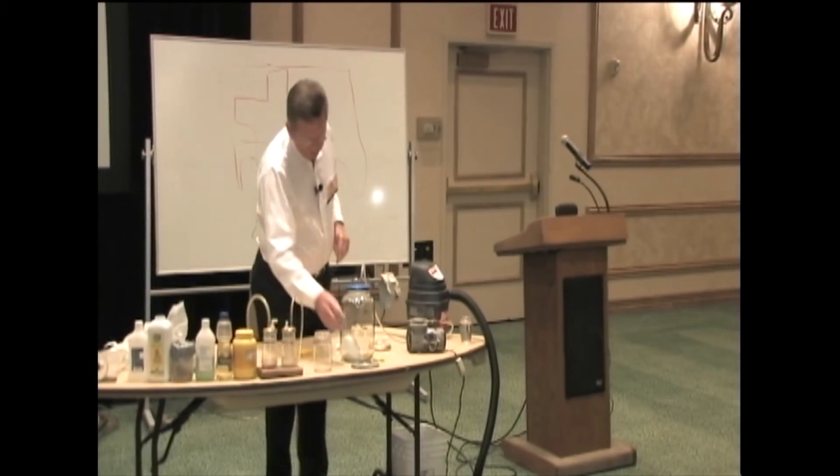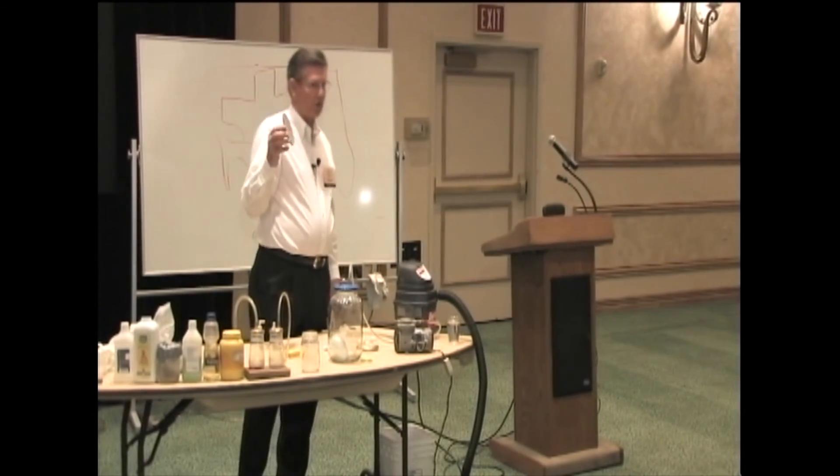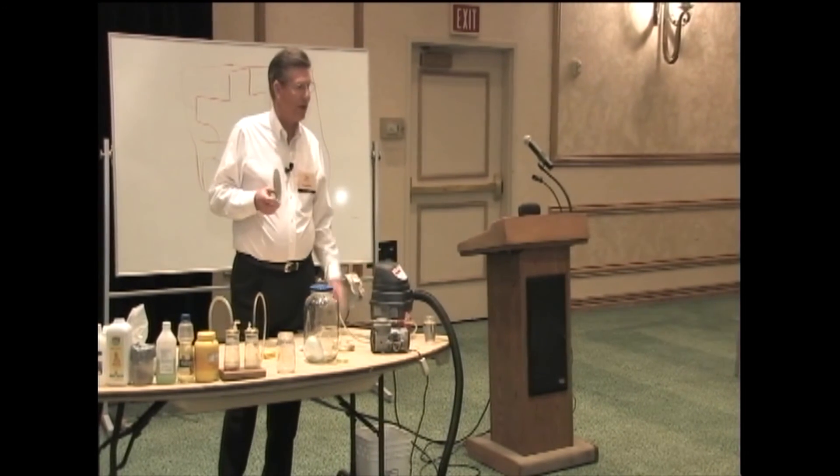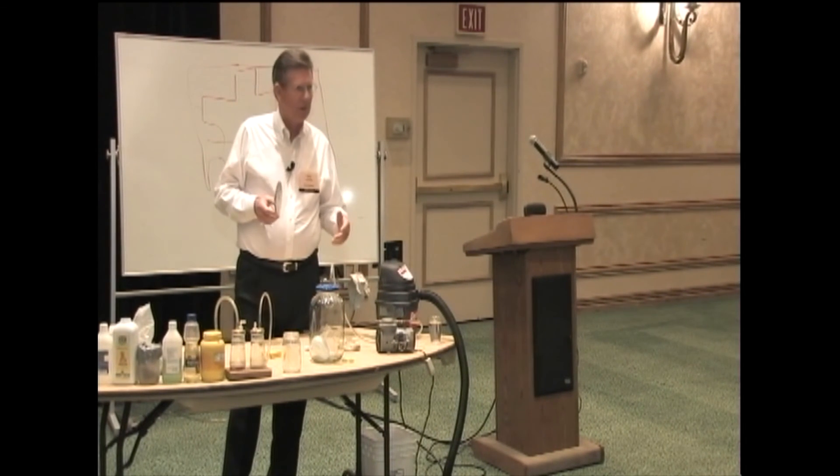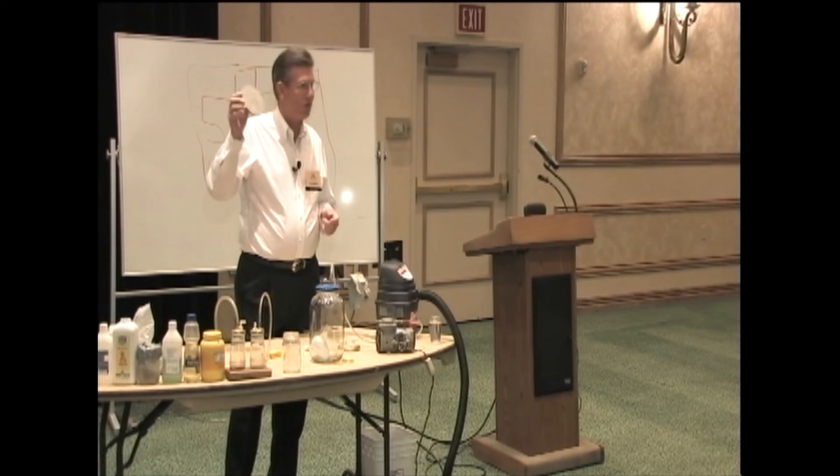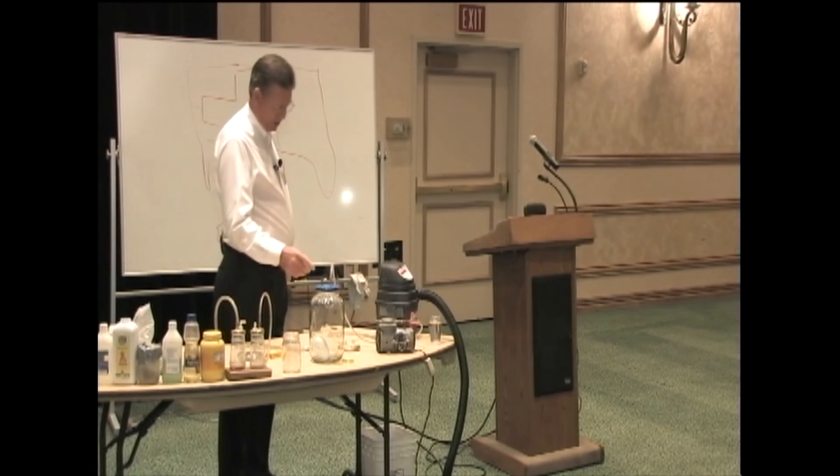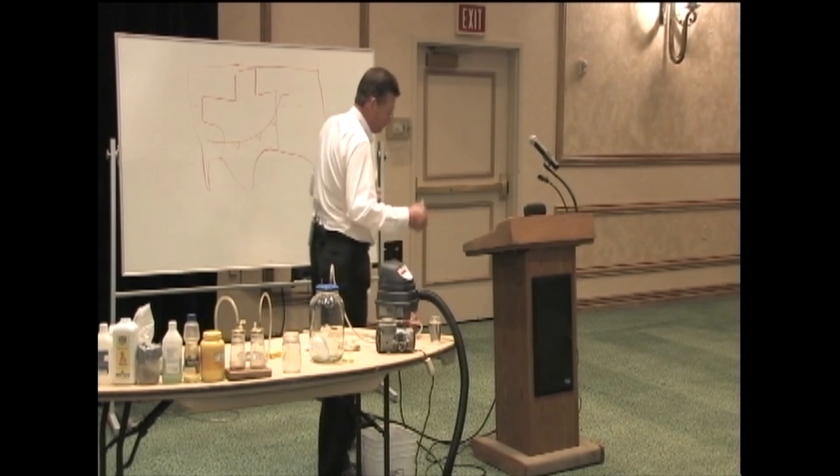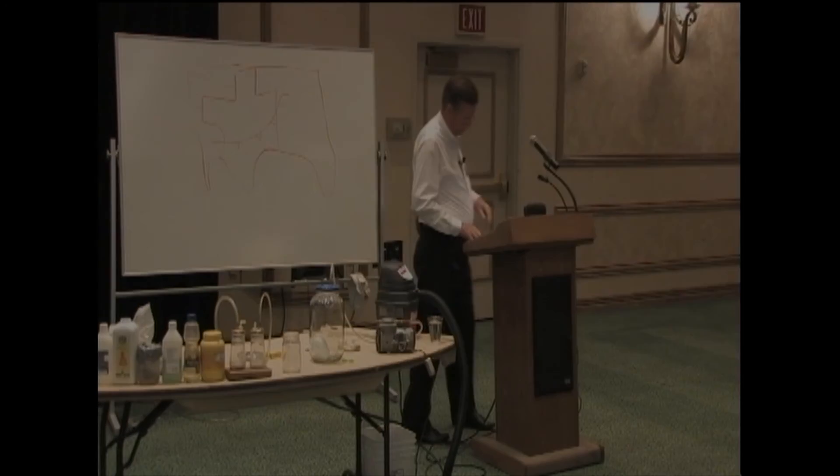But we use a centrifugal fan, also sometimes we use big PD blowers. This is neither one. There's more than one way to produce a vacuum. You can do it with rotary sliding vanes, you can do it with centrifugal fans, you can do it with rotary lobe blowers. This happens to be just a diaphragm vacuum pump.